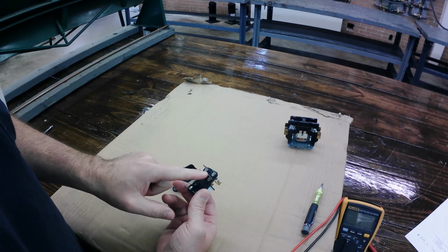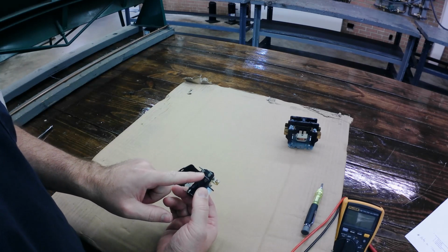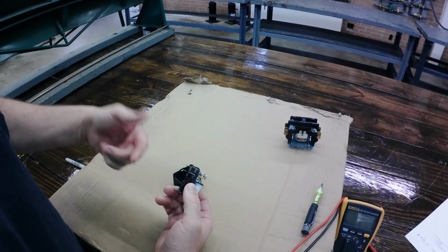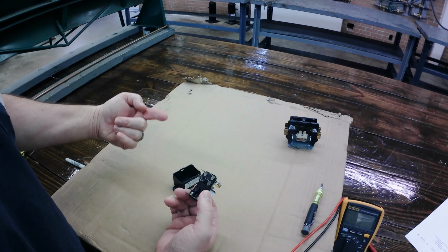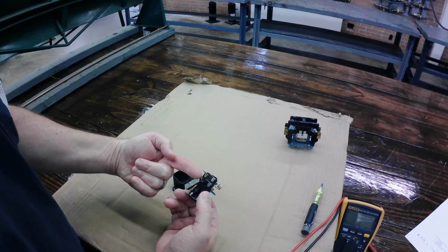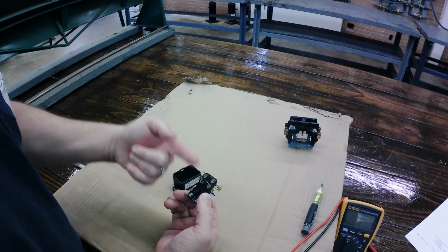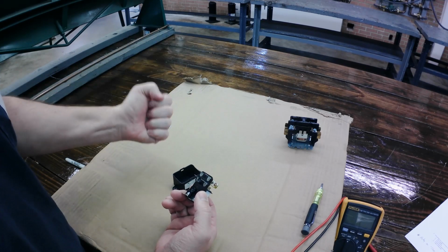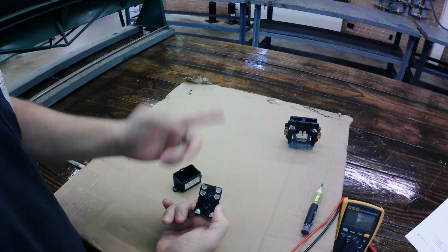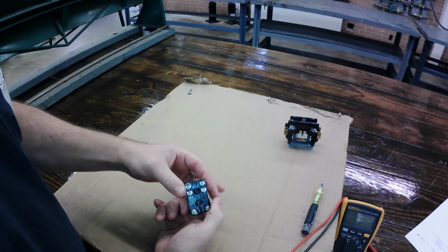And then we'll probably use the normally closed switch to tie into our heat sequencer, so that when the heat strips come on, we can send power from that high voltage heater circuit through the normally closed to get our fan to come on with the heat strip. So typical stuff, nothing fancy.